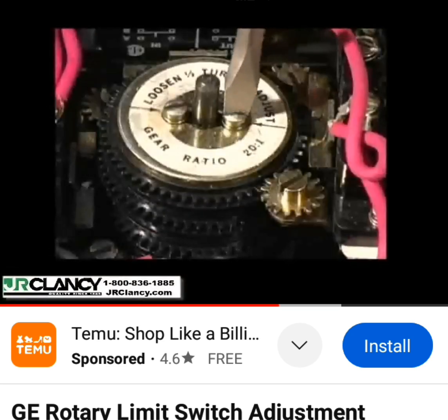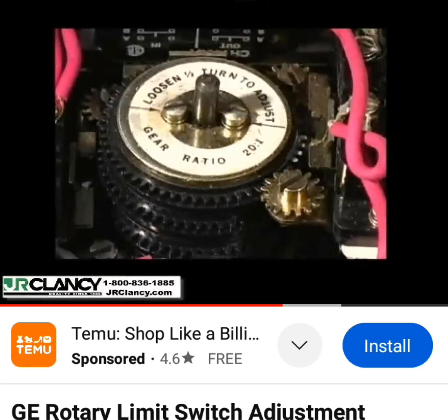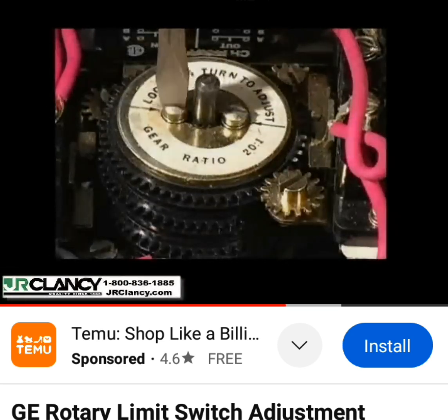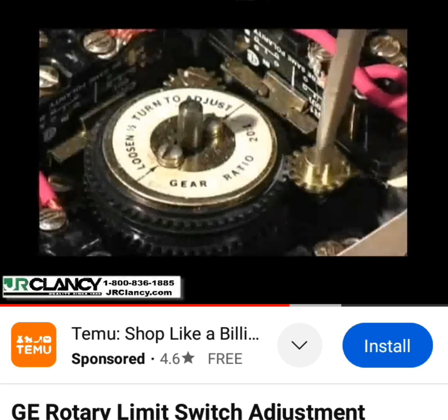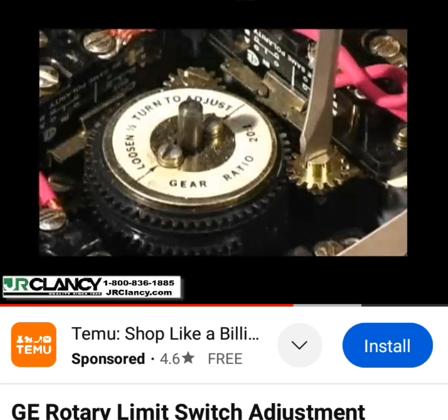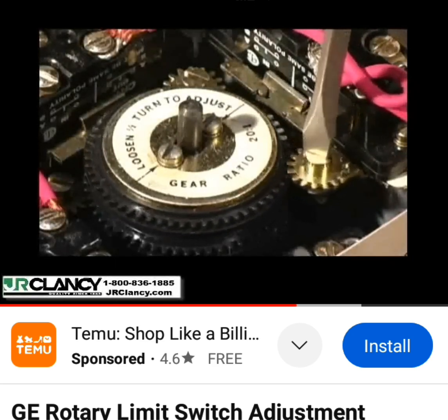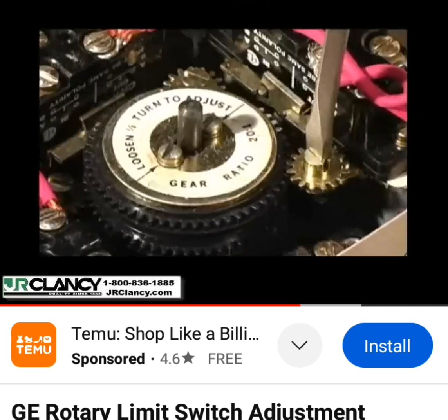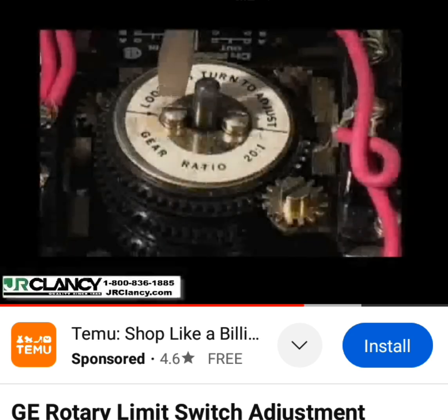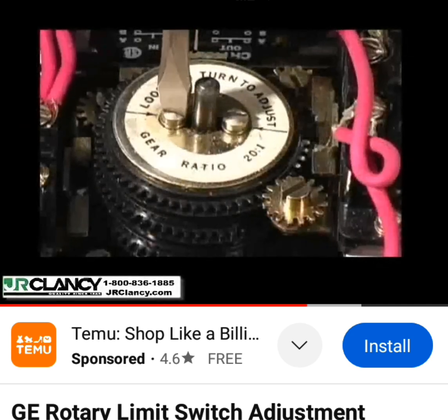Loosen the cam stack clamping screws 1/2 turn. Use the pinion that is located clockwise to the switch to then adjust the cam stack slice. When the lobe contacts the switch, an audible click will be heard. Complete the process by tightening the cam stack clamping screws.